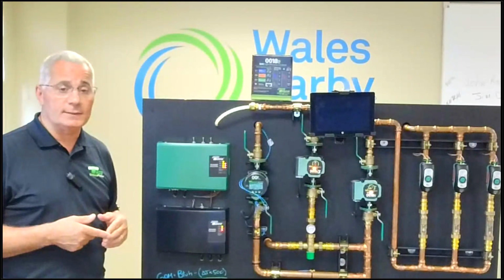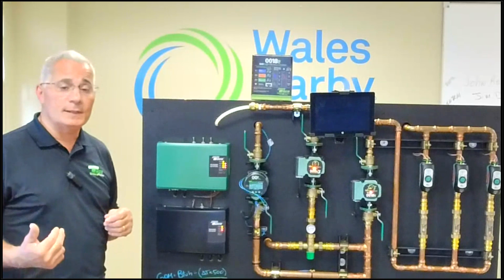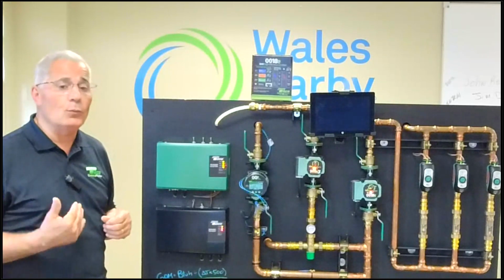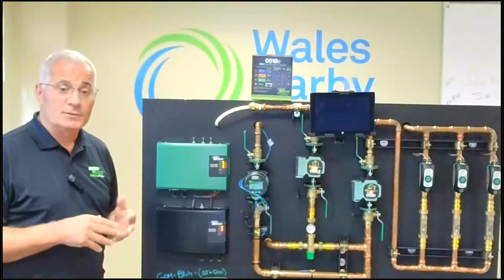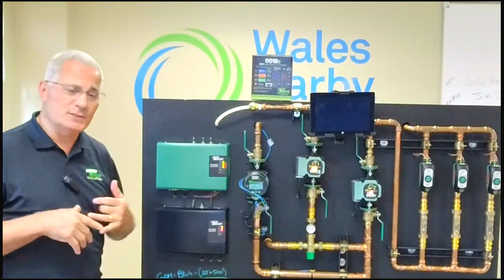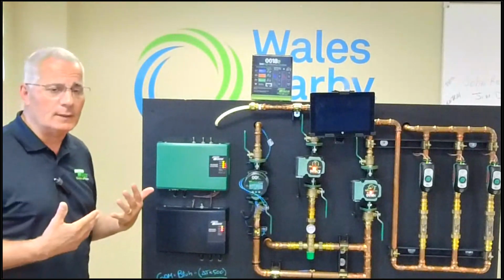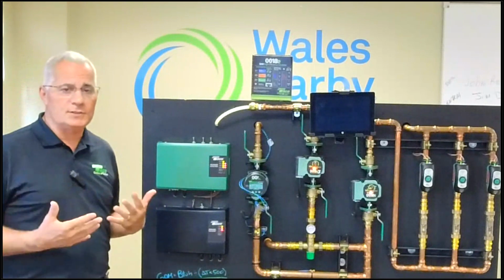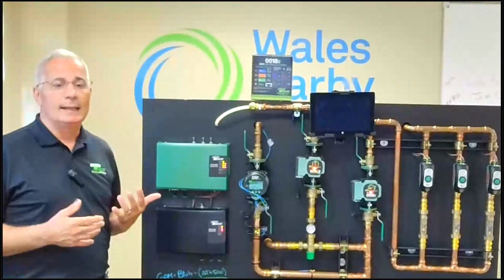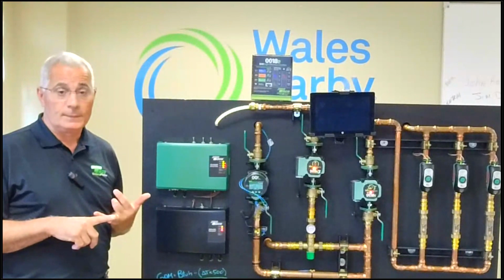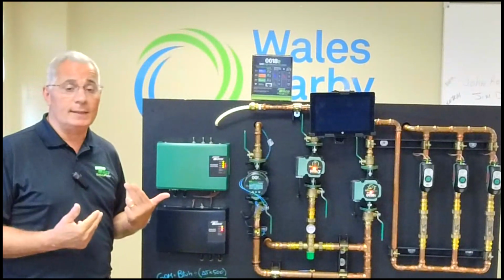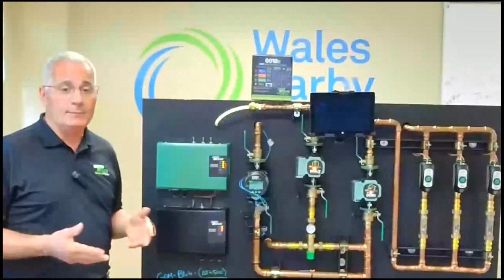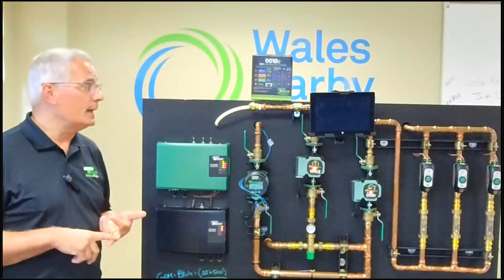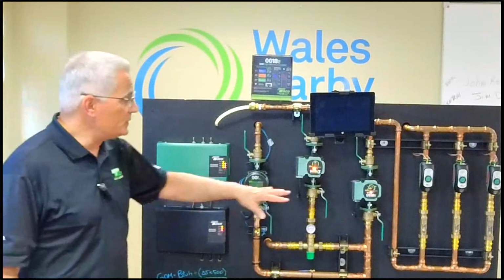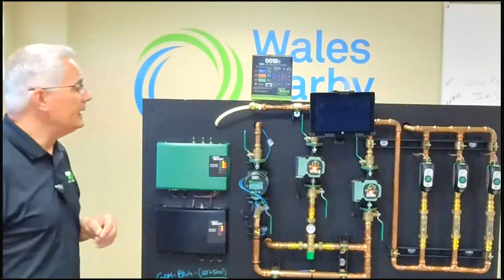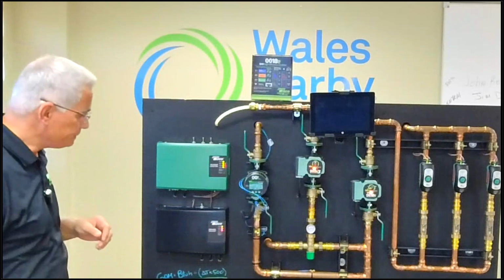It'll run the circulator, and until that return water temperature gets below 140, it won't turn on the boiler. So that's another way of saving energy, because the idea again with this webinar is total energy savings. How are we doing that? And that is electrical and it is fuel. So if it was natural gas or propane or even oil, if I can keep the boiler off, not only am I saving power, I am saving fuel. So that's what you see here on the cast iron side of things, okay?